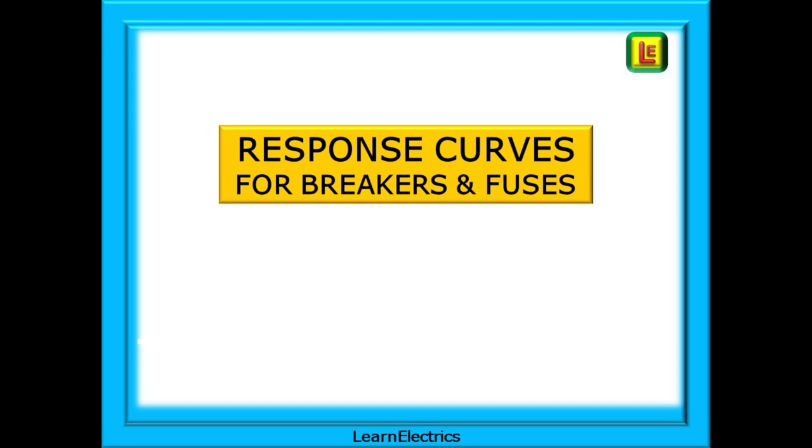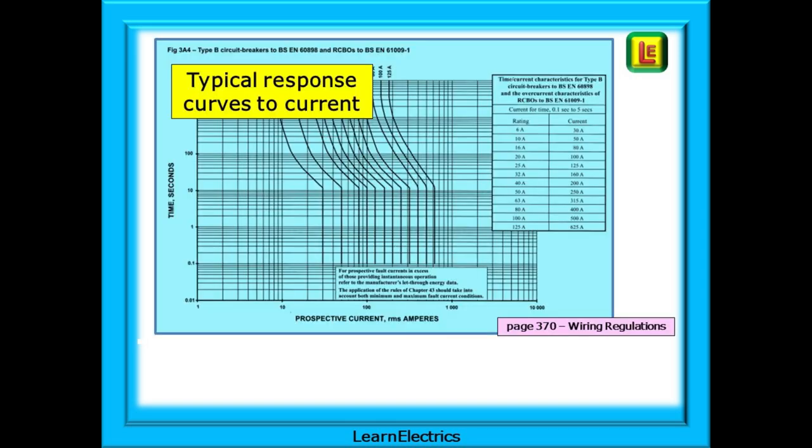We must look at the response curves of circuit breakers and fuses next since it is the response curve that determines what type of overcurrent the breaker is actually looking at. The response curve dictates if the breaker operates immediately or whether it can take its time and trip after 10 minutes or so. This is a typical response curve taken from the wiring regulations book. Each type of fuse or breaker will have their own page and each rating of fuse or breaker will have its own curve. These are the curves that all manufacturers will make a breaker work to. It is their standard. Let's simplify this.